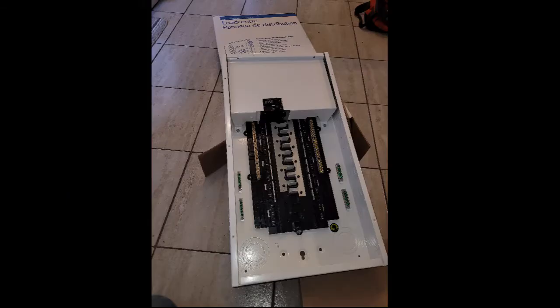The electrical panel we're going to use here is the Eaton load center, 20/40 circuits with a 100 amp main breaker for 120 and 240 volts. The reason we chose this one is, first, it's very cost effective and from a very reliable manufacturer. We can use the reliable Cutler-Hammer circuit breakers, and there's enough room for future upgrade, enough circuits, and after the load calculation, we know we can even do an EV charger for this property.